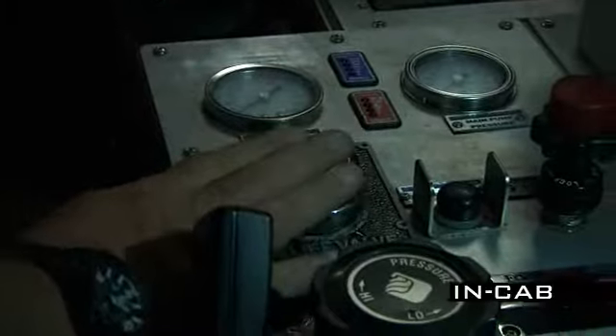If this valve is loose, you also will not generate pressure, so ensure when you put it back in that everything is screwed snugly, and it just needs to be hand tight. You should not need to use a wrench. This is always done when the pump is off.